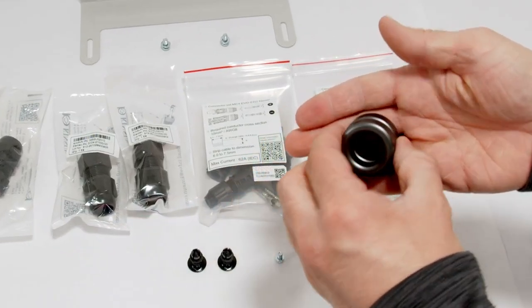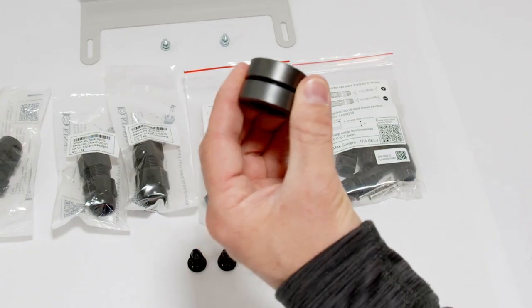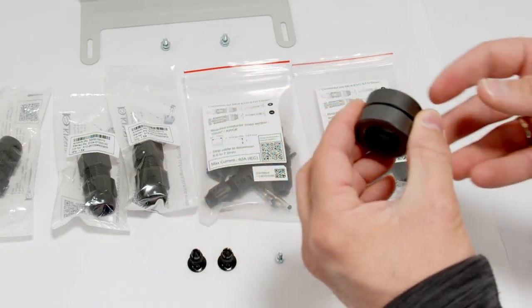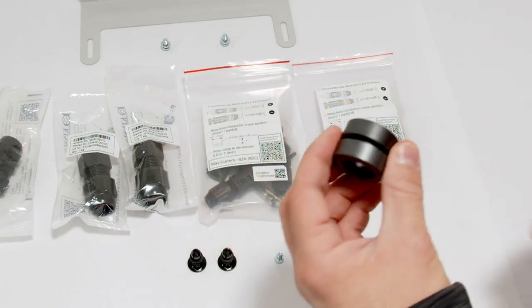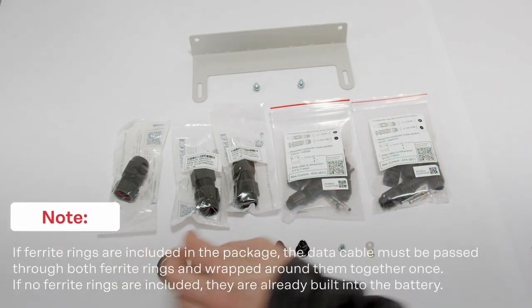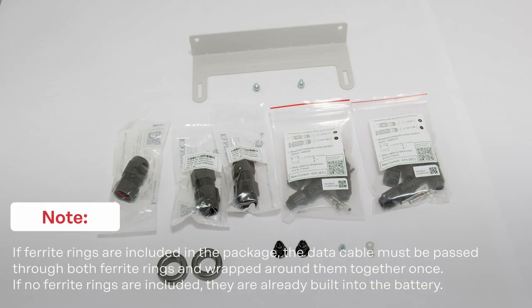Please note, whenever you have these ferrite rings within the scope of delivery of your battery, you need to install them on the data communication cable 2 times that goes to the inverter of the system. Please note, whenever you don't have these ferrite rings in the scope of delivery, that means that you have a newer system where the ferrite rings are already integrated in the battery management unit of the system, so no need to install them externally.